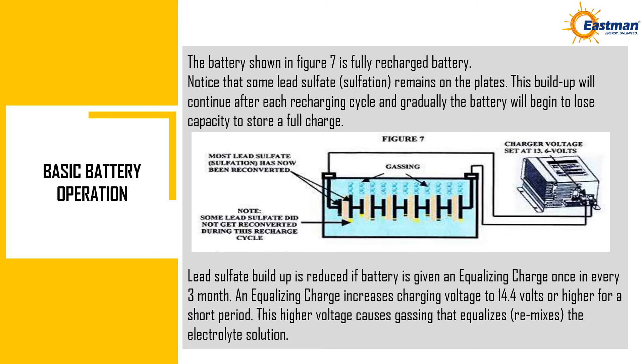Notice that some lead sulfate remains on the plates after recharging. This buildup continues after each recharging cycle and gradually the battery loses capacity to store a full charge. Lead sulfate buildup is reduced if the battery is given an equalizing charge once every three months. An equalizing charge increases charging voltage to 14.4 volts or higher for a short period. This higher voltage causes gassing that equalizes and remixes the electrolyte solution.